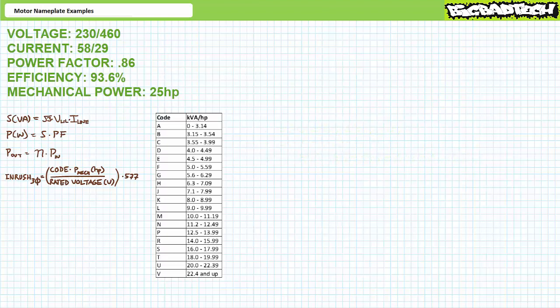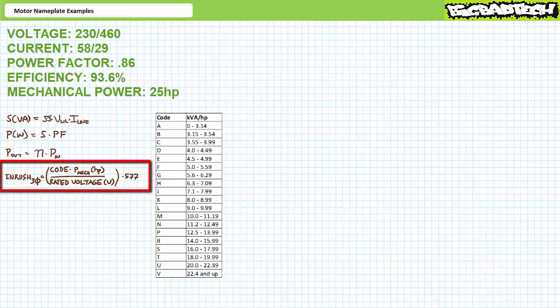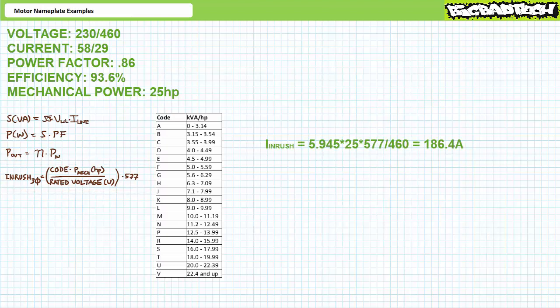Let's now calculate the inrush experienced by this motor upon closure of a direct-online full voltage starter, for the high voltage configuration. An inrush code of G represents a constant of 5.6 to 6.29 — we'll use the midpoint of 5.945. Inrush current is estimated as: inrush = code constant × motor horsepower ÷ (rated voltage × √3). Substituting these values, one would expect an inrush of approximately 186.4 amps in the high voltage configuration. Luckily this surge doesn't last long.